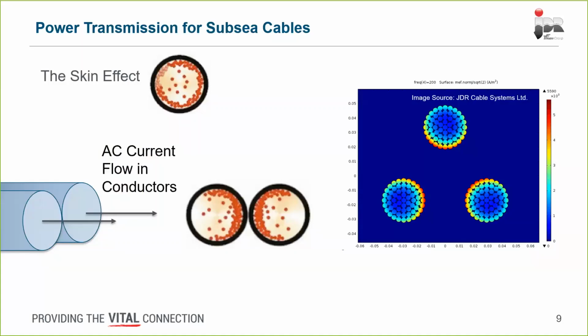Maybe 2.5 if you're looking at something that gives you a bit of power. The conductor sizes that we're talking about for floating wind are up to 1,000 millimeters squared. So that puts a bit of perspective in how large we're talking. But as we increase the size of the conductor, we've got to account for the skin effect. When we have current flowing through a conductor, the resultant magnetic field forces the electrons towards the outside of the conductor, which increases the resistance and the inductance.